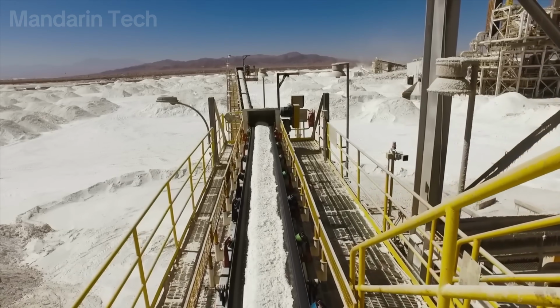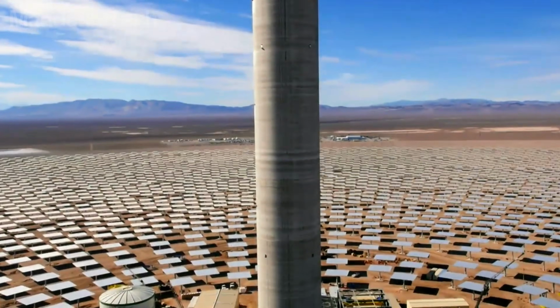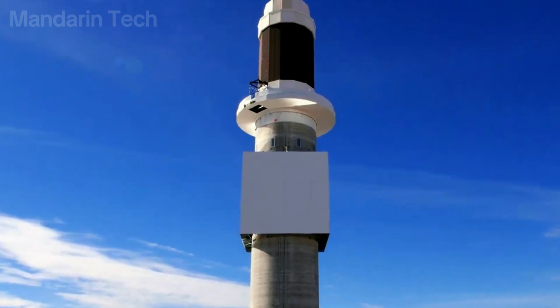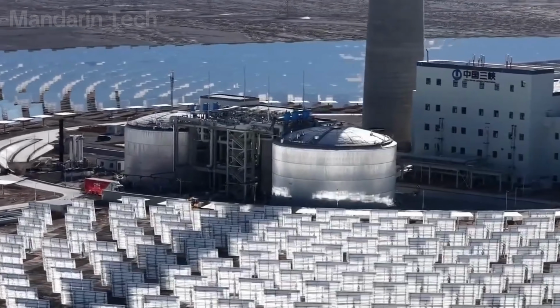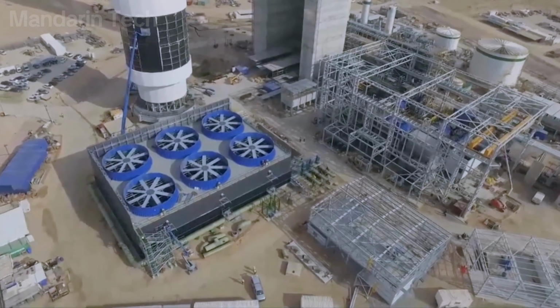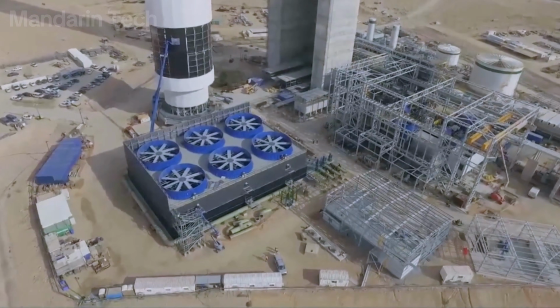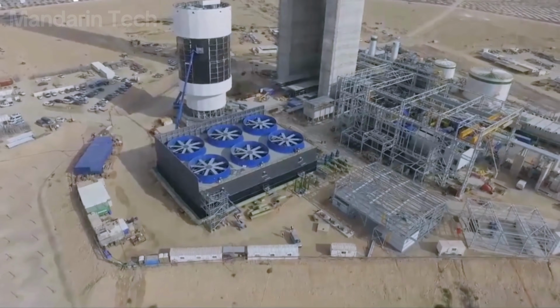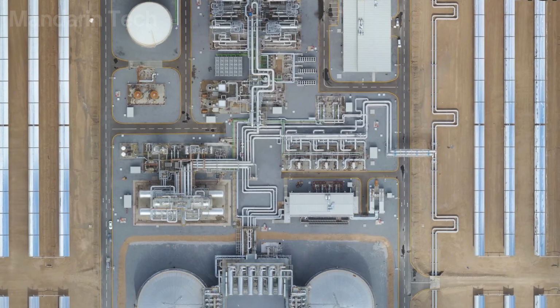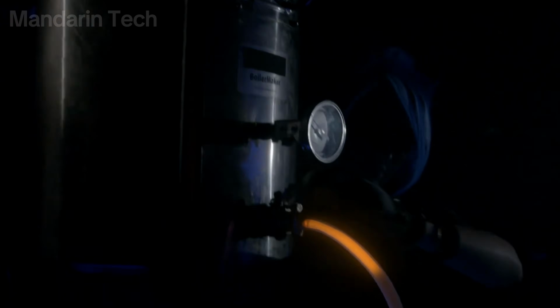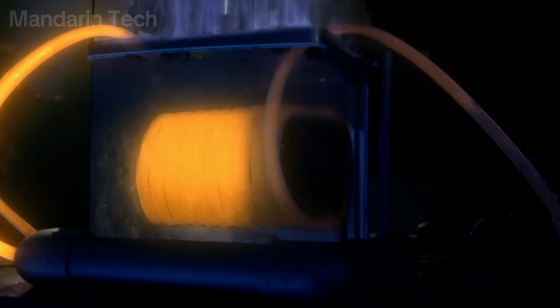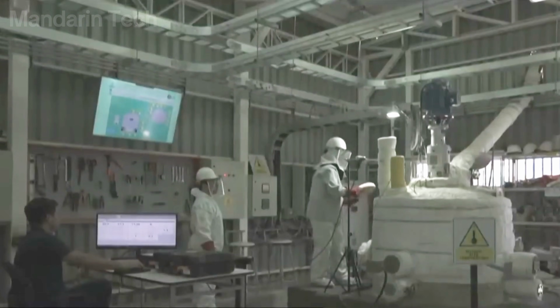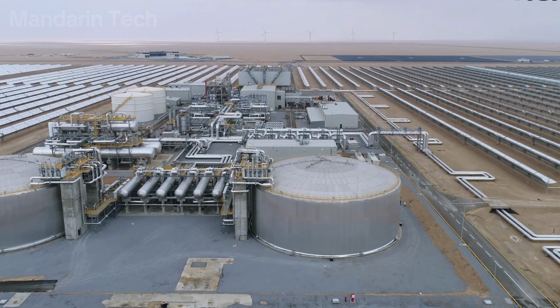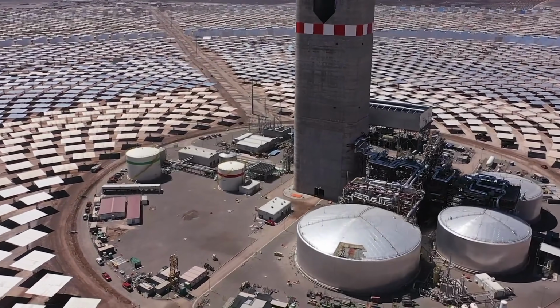Salt from the cold tank was pumped up to the receiver, heated to around 565 degrees Celsius, and then flowed back into the hot tank. During power generation, the heat was transferred to water to produce steam that drove the turbine, while the cooled salt returned to the original tank. Finally, 46,000 tons of salt were melted in batches, while the pipelines were preheated to prevent solidification. Cerro Dominador's thermal storage system was ready for operation.